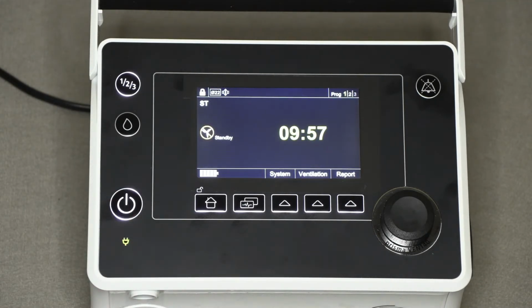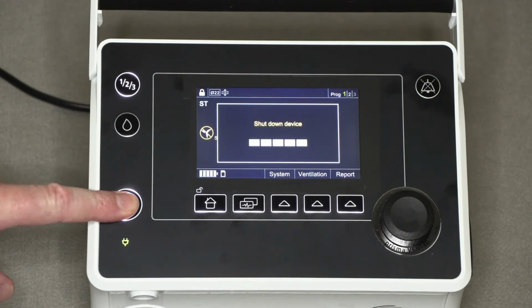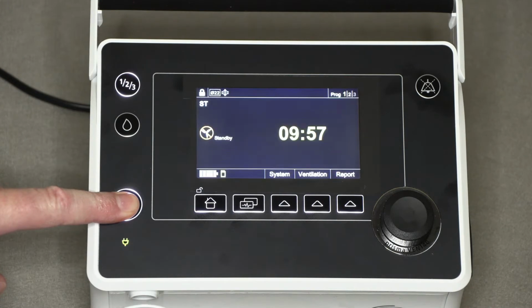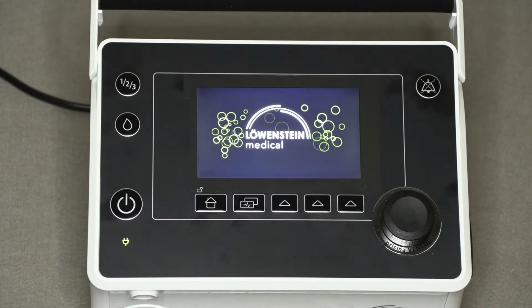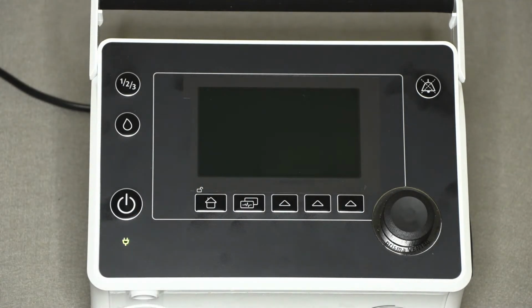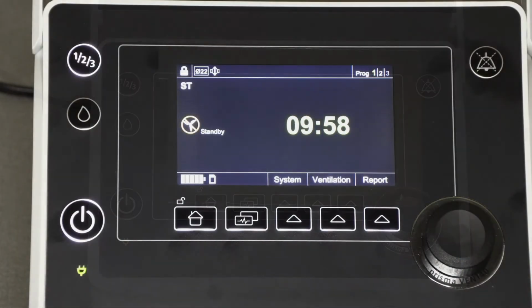If you then want to shut the ventilator down completely, again press and hold the power button. So, a quick depress of the power button will either turn prismaVENT 40 from off into standby mode, or start therapy if it's already in standby mode. And by pressing and holding the power button, you will stop therapy if therapy is running, or shut the device down completely if it's in standby mode. This ventilator is currently in standby mode.